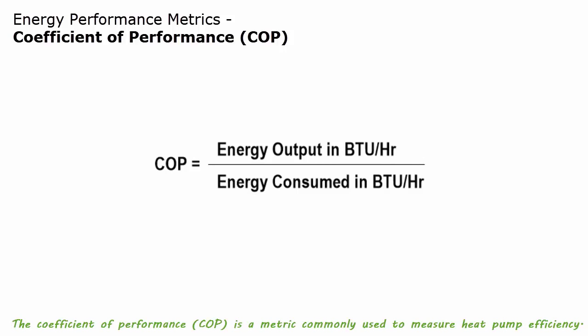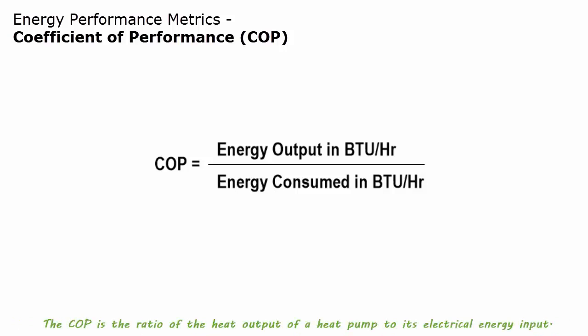The coefficient of performance, COP, is a metric commonly used to measure heat pump efficiency. The COP is the ratio of the heat output of a heat pump to its electrical energy input. Higher COPs equate to lower operating costs. Air source heat pumps generally have COPs ranging from 2 to 4, meaning that they deliver 2 to 4 times the energy they consume. Water source and ground source heat pumps normally have COPs ranging from 3 to 5. The COP of an air source heat pump decreases as the outdoor temperature drops. Therefore, 2 COP ratings are usually given for a system, one at 47 degrees F and one at 17 degrees F.